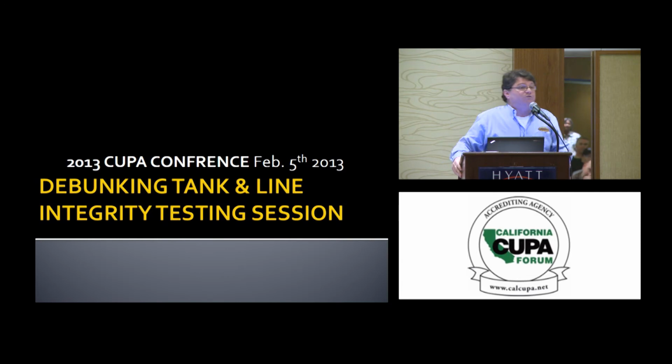We recreate a leak to verify. One of the things we train in the Petrotite class is that we want to sweat a plug, we call it. We actually loosen the plug while we have an inspector or somebody on site to create a leak, a small leak, so that our equipment would have found it. We are trying to calibrate every time we test to show we could find a leak.